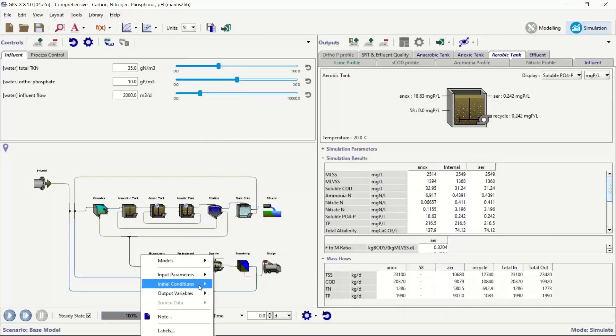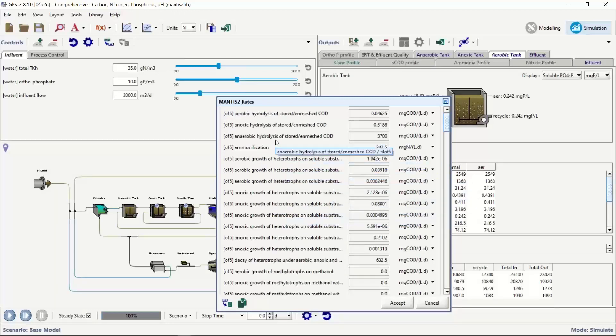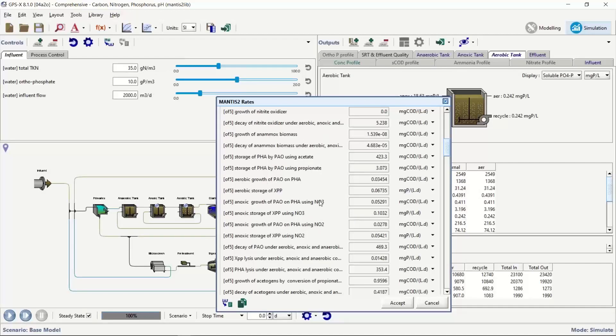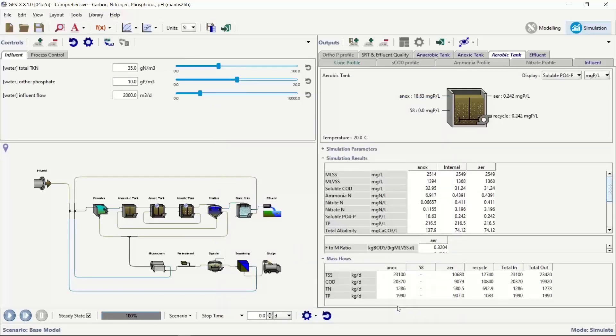For the digester, going to the same Mantis II Rates menu, we can see there's lots of hydrolysis happening because it's an anaerobic environment, no growth of bioP bugs of any kind, but decay of bugs is occurring. In the precipitation section, there's struvite — that's the big number showing what's happening. When working on complicated activated sludge systems with two, three, four, or five different kinds of biomass, if a concentration in versus out isn't telling you the whole story, going to that Mantis II Rates menu is really useful to see which processes are most significant in that particular unit, even if just comparing relative rates.